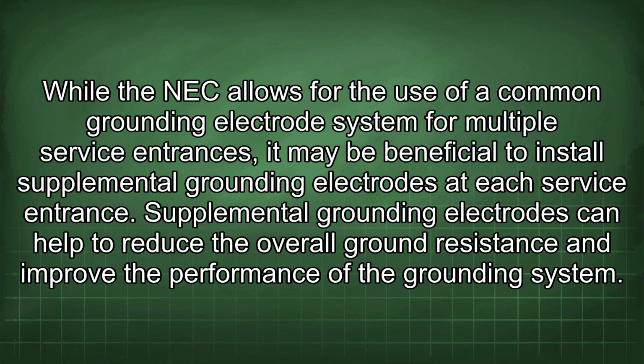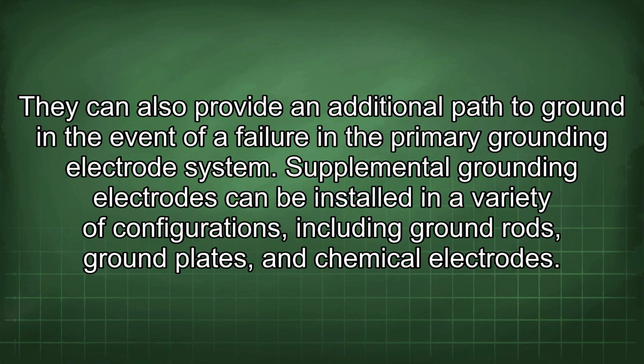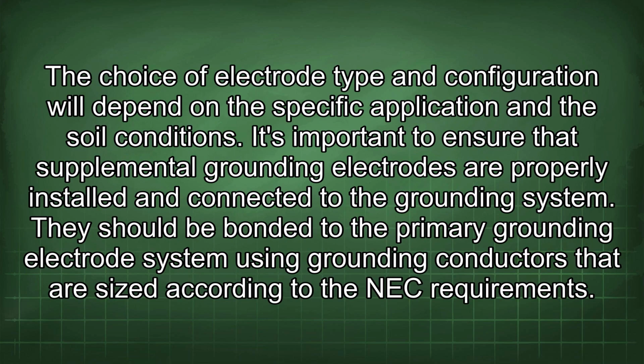Supplemental grounding electrodes can help to reduce the overall ground resistance and improve the performance of the grounding system. They can also provide an additional path to ground in the event of a failure in the primary grounding electrode system. Supplemental grounding electrodes can be installed in a variety of configurations, including ground rods, ground plates, and chemical electrodes. The choice of electrode type and configuration will depend on the specific application and the soil conditions.